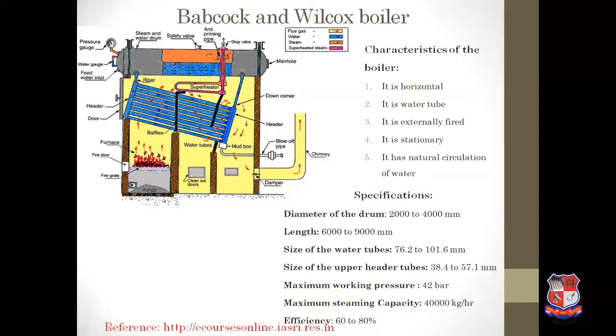A safety valve — either a dead weight safety valve or a lever-loaded safety valve — releases pressure when the steam pressure level is above a certain level. A stop valve supplies the generated steam to the necessary place, such as a steam turbine. A superheater is also provided to superheat the steam, and this superheated steam is supplied to the steam turbine. The superheater takes heat from the hot gases.